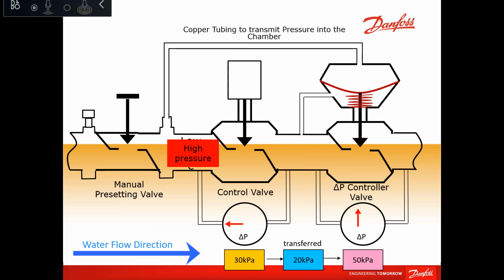It's a two-way valve plus DPCV. The setting mechanism is the same as the control part, while some manufacturers make it different from the control part. If the control part is the same as the flow setting mechanism, you are only required to maintain a fixed differential pressure across one globe valve and seat. If you have two separate parts, one to set the flow and one to control the flow, the DPCV of the PICV should maintain a fixed differential pressure across two valves. How the pressure is distributed between these two valves, you cannot judge. If the setting is low, you will have low authority on the control valve. If the setting is high, there will be a big effect, which means these kinds of technologies are effective up to 70% setting. If it is less, then it might compromise the pressure independency itself.